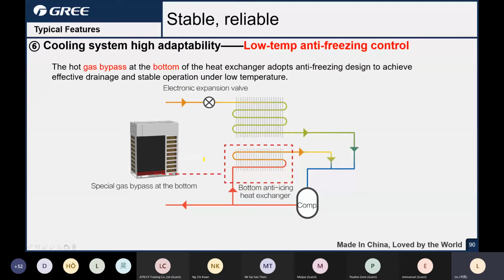Okay, next one is about defrosting. For the VRF, defrosting is a very headache problem in winter, and normally the units will switch to cooling to do the defrosting. However, for GMV6, there is a special gas bypass copper pipe from the discharge at the bottom. You can see here this compressor, this is the discharge. This is a special copper pipe stretching to the chassis, the VRF chassis. So in winter, there is a solenoid valve here. It will open to distribute some hot gas to eliminate the ice and frost in the chassis. That's the low temperature anti-freezing control.